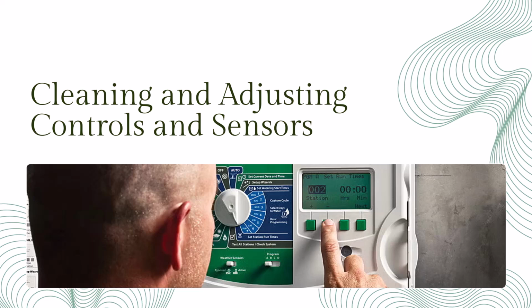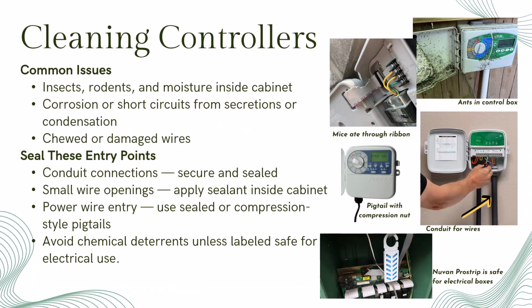which do not, safely remove debris and seal entry points that invite insects or moisture, adjust controllers, reset power devices like GFCIs and circuit breakers, and verify sensor accuracy. By the end, you'll know how to maintain both the hardware and programming aspects of irrigation control systems to prevent damage and improve reliability. Controllers can attract more than just water.